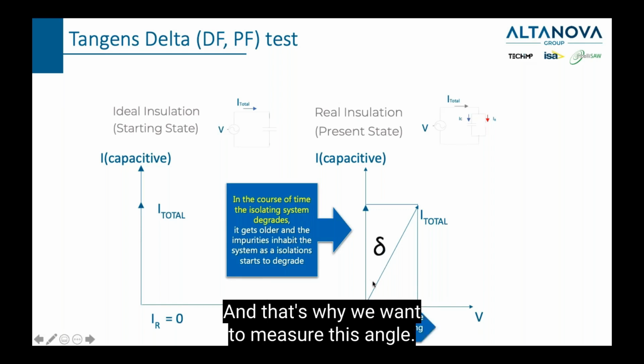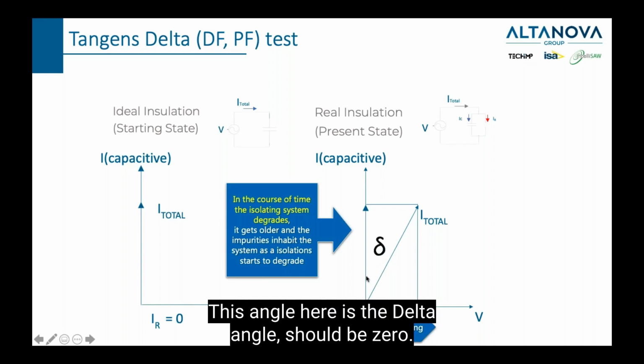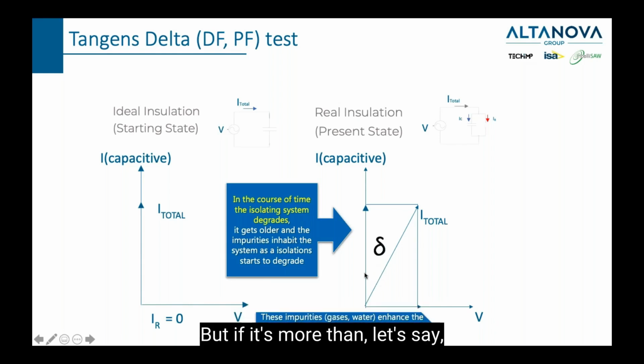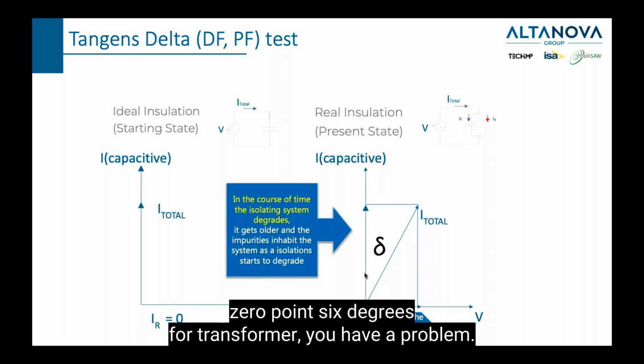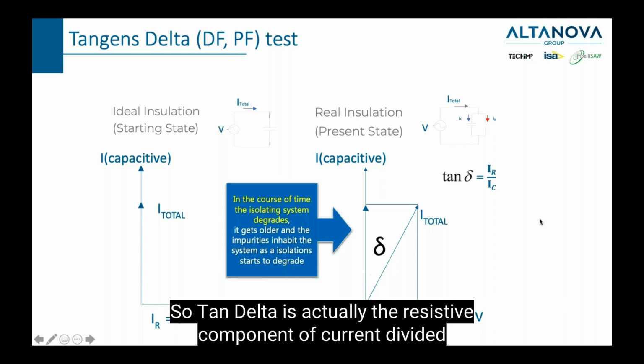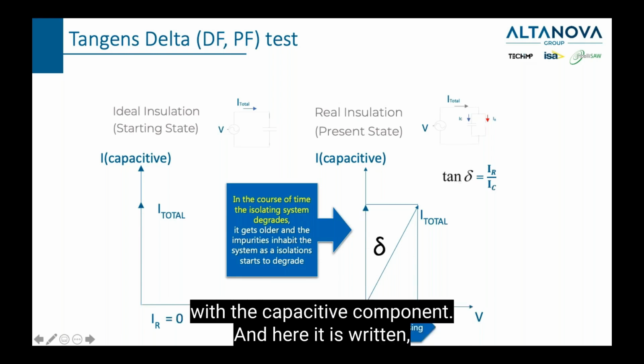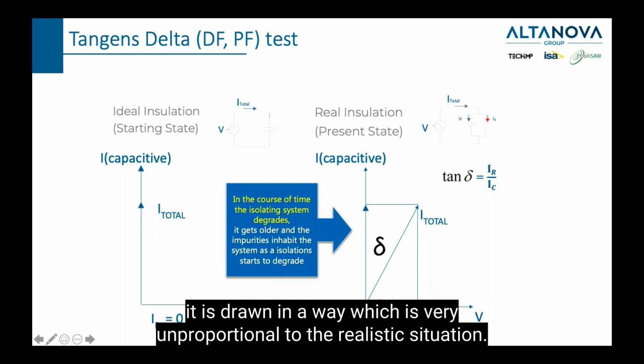And that's why we want to measure this angle. This angle here is the delta angle. It should be 0. But if it's more than, let's say, 0.6 degrees, for a transformer, you have a problem. So tan delta is actually the resistive component of current divided by the capacitive component. And here it is drawn in a way which is very disproportionate to the realistic situation.